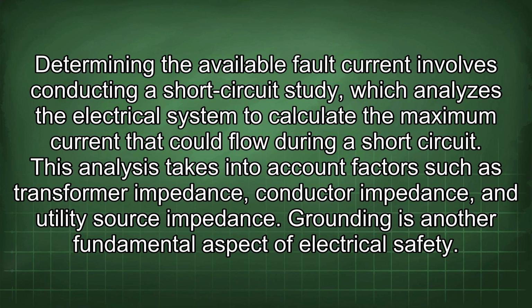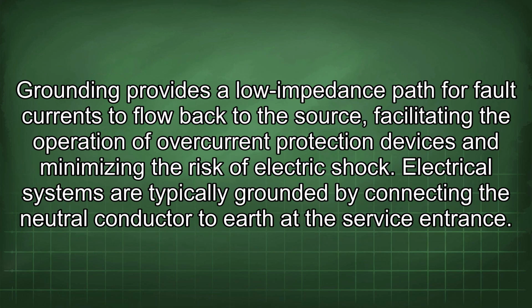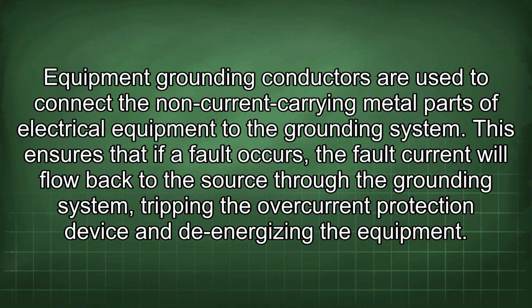Grounding is another fundamental aspect of electrical safety. Grounding provides a low impedance path for fault currents to flow back to the source, facilitating the operation of overcurrent protection devices and minimizing the risk of electric shock. Electrical systems are typically grounded by connecting the neutral conductor to earth at the service entrance. Equipment grounding conductors are used to connect the non-current carrying metal parts of electrical equipment to the grounding system. This ensures that if a fault occurs, the fault current will flow back to the source through the grounding system, tripping the overcurrent protection device and de-energizing the equipment.